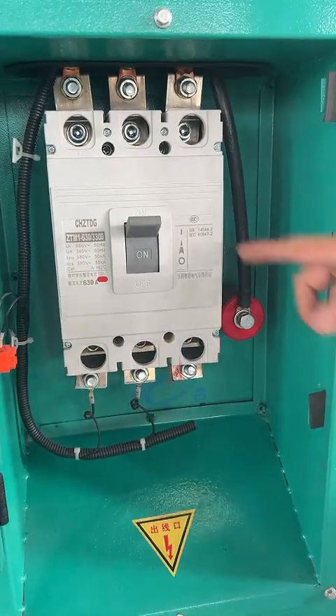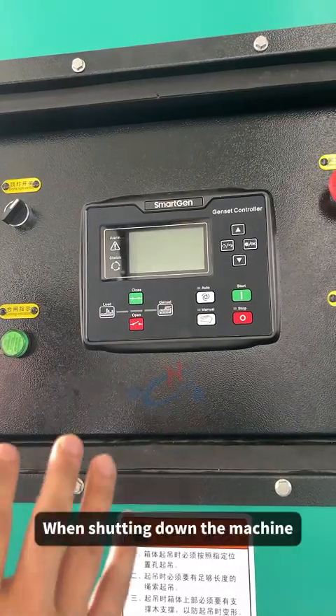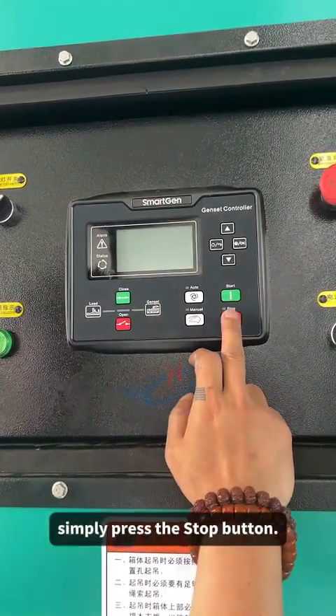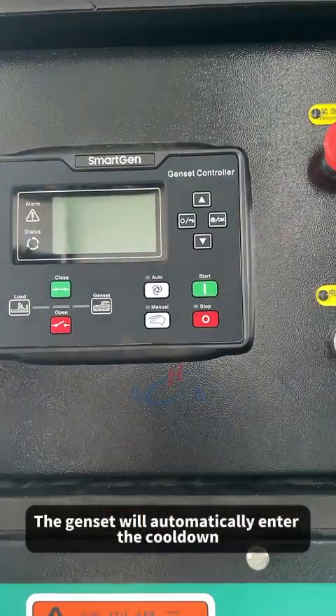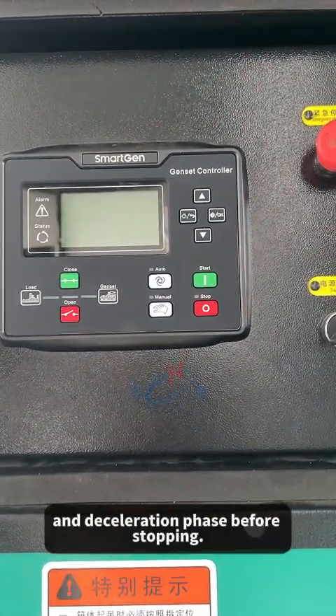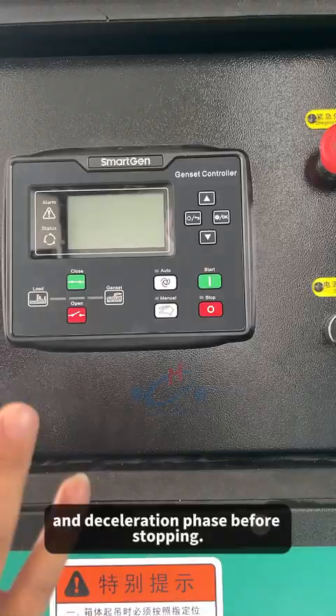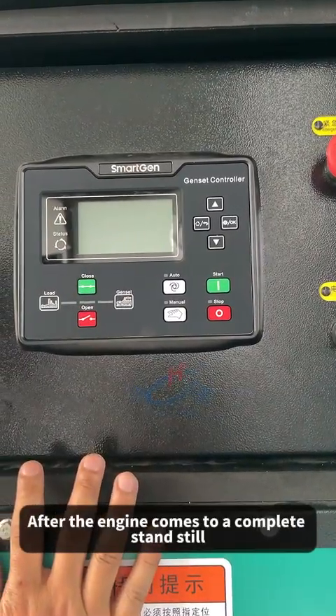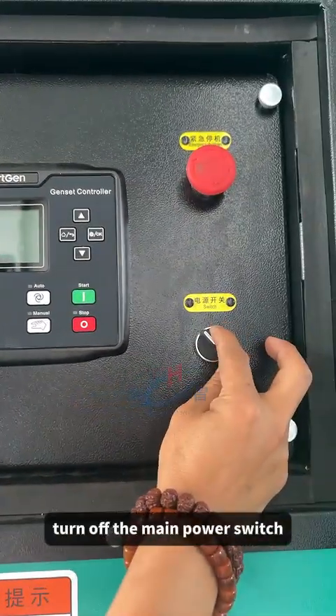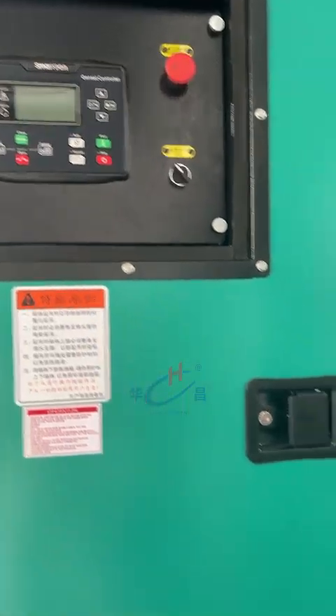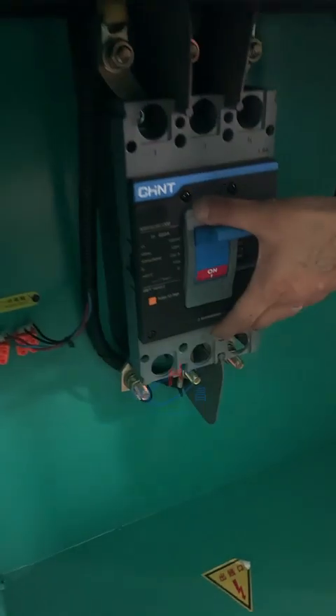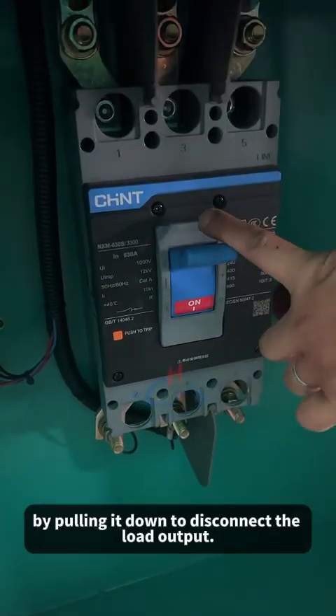Applying load. When shutting down the machine, simply press the stop button. The genset will automatically enter the cool down and deceleration phase before stopping. After the engine comes to a complete standstill, turn off the main power switch and then turn off the circuit breaker by pulling it down to disconnect the load output.